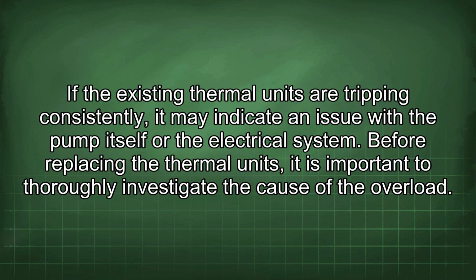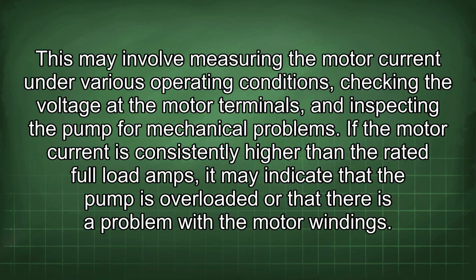If the existing thermal units are tripping consistently, it may indicate an issue with the pump itself or the electrical system. Before replacing the thermal units, it is important to thoroughly investigate the cause of the overload. This may involve measuring the motor current under various operating conditions, checking the voltage at the motor terminals, and inspecting the pump for mechanical problems. If the motor current is consistently higher than the rated full load amps, it may indicate that the pump is overloaded or that there is a problem with the motor windings.